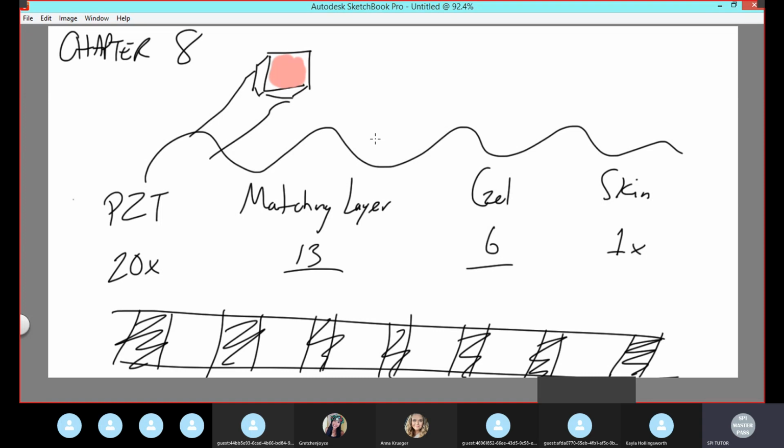We don't sterilize it, we disinfect it. Because sterilization, and we'll talk about that in other chapters, can damage that. And if it damages that, it damages the bridge. And now waves may not be able to make it to the other side, and then your transducer is done for. I think it's like $10,000, $15,000 to replace it. So it's very expensive.